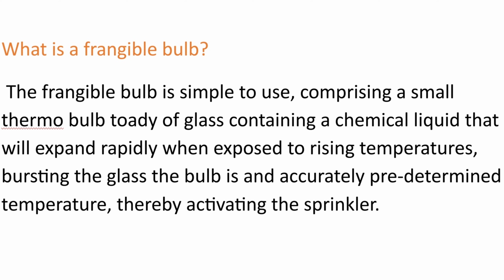What is a frangible bulb? The frangible bulb is simple in design, comprising a small thermobulb of glass containing a chemical liquid that will expand rapidly when exposed to rising temperatures, bursting the glass at an accurately predetermined temperature, thereby activating the sprinkler.